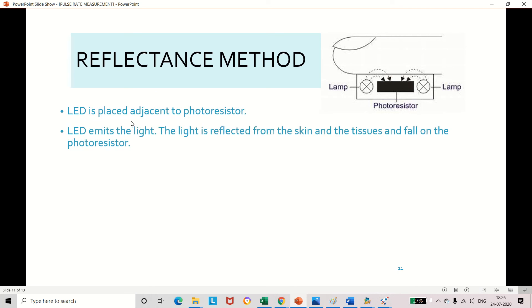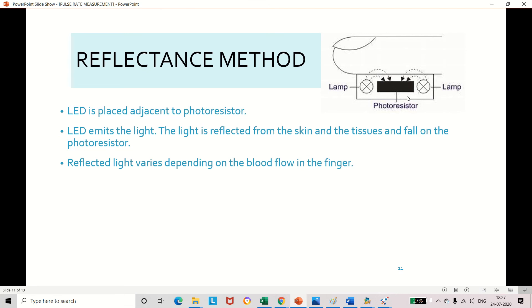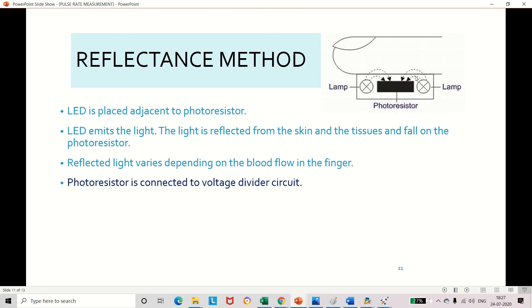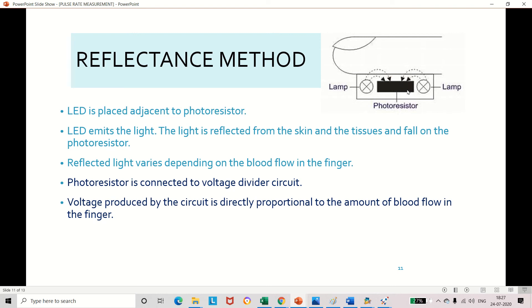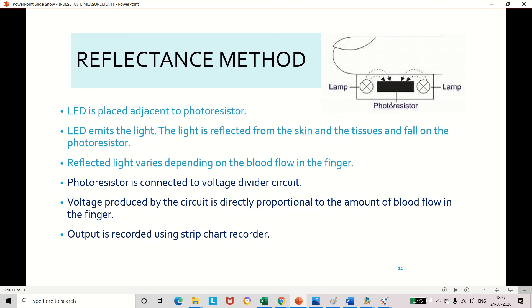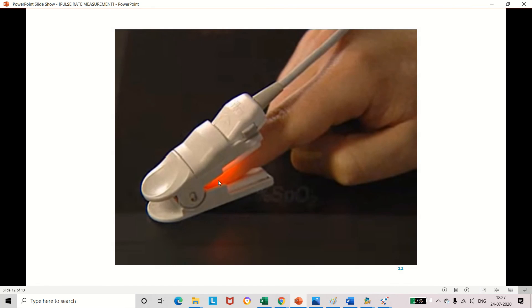To summarize the reflectance method: the LED is placed adjacent to the photoresistor. The LED emits light that touches the surface of the skin and is reflected back onto the photoresistor. Due to the reflected light, the resistance changes, and using the voltage divider circuit, the voltage changes depending on the blood flow in the finger. We can record this pulse waveform using a strip chart recorder. This is also the principle used in the real-time device where we insert the fingertip to measure the pulse rate.